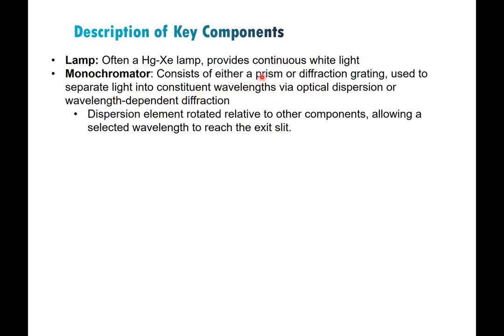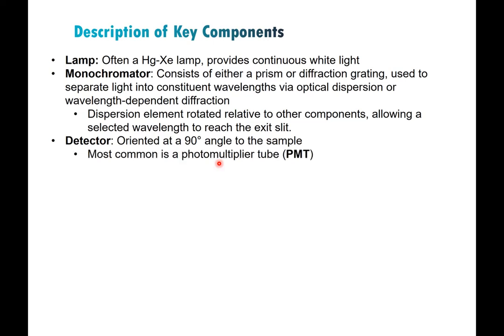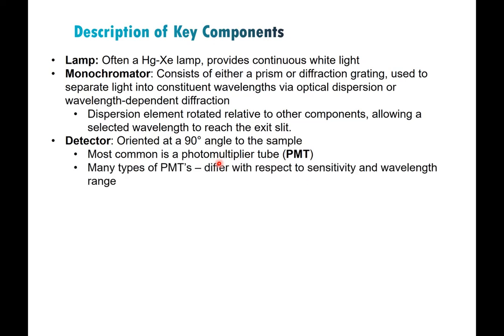The grating or prism is rotated relative to the other components to determine which wavelength actually reaches the exit slits — that noise you hear is the grating moving to direct the correct wavelength out. The detector is 90 degrees relative to the excitation, on one side of the sample. The most common type is a PMT — photomultiplier tube — and that's the type we have on Flora One and Flora Two. Different PMTs differ with respect to sensitivity and the range of wavelengths they can detect. The one on Flora One is an R928, one of the most common found in fluorometers; Flora Two has a different one that detects a wider range.